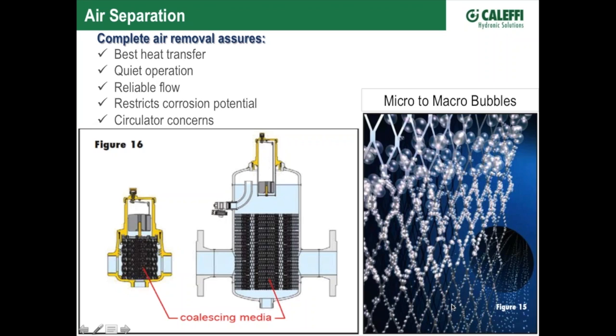It's also important to make sure that it's quiet. We don't want to hear bubbles gurgling through our heat emitters at night when we're trying to sleep. We want to make sure that we've reduced the potential for corrosion problems. Air in the water can cause additional corrosion problems. And of course, we want to protect our circulators. They move water, not air. So we want to make sure we get the air bubbles out.